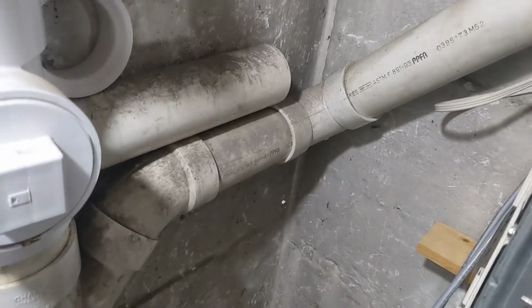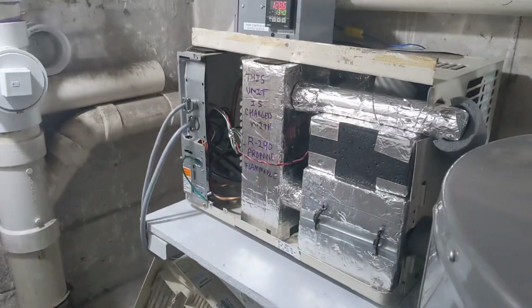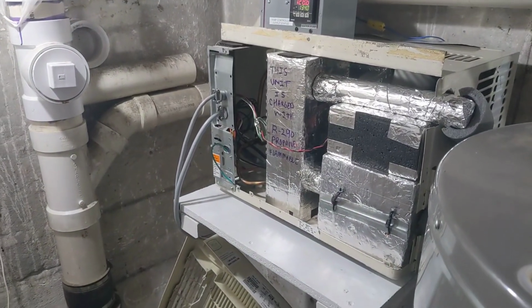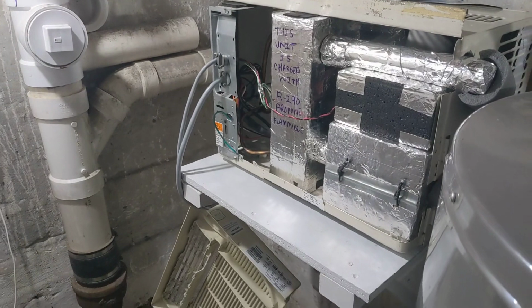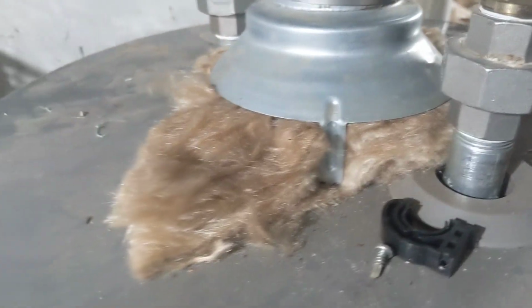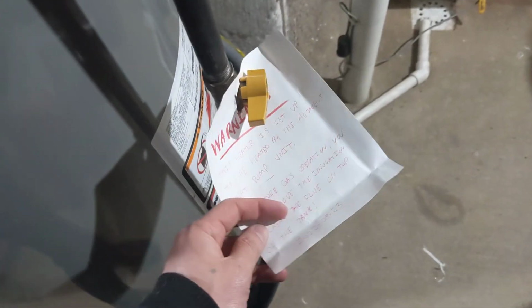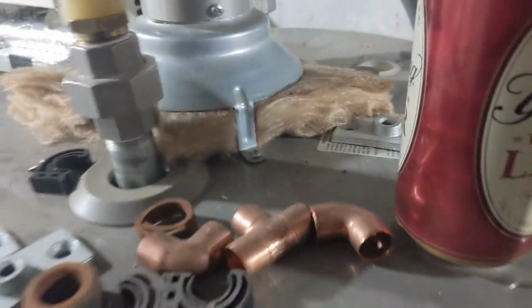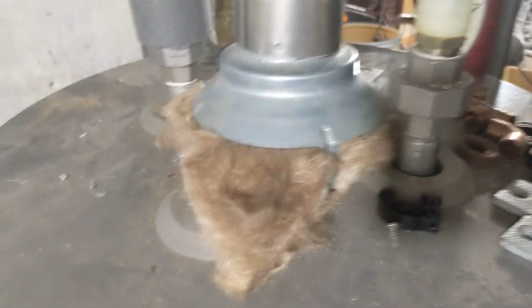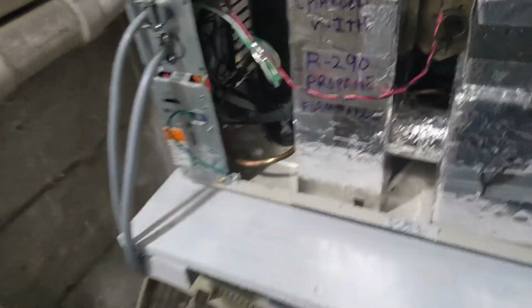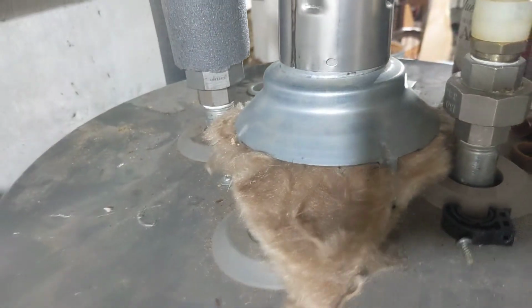So that's it. That's the heat pump water heater update. This thing has basically been running for 3 months now. All hot water. There is no gas being used at all. It's actually shut off. So I even blocked off the exhaust. And that's why there's a label here in the event that it was ever necessary that somebody would know. The exhaust is blocked. You got to unblock the exhaust before you fire up the water heater. Just take that piece of insulation out of there. That's all it is. So that's it.